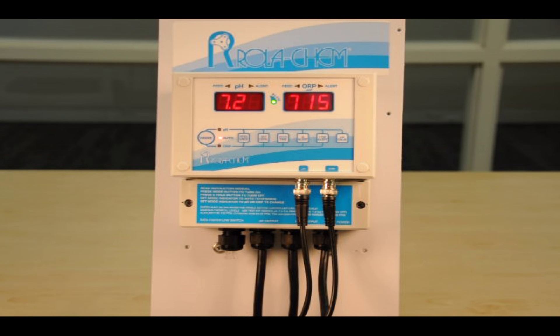In this segment I want to show you where the fuses are located for the 554 series Rola-Chem controller. The fuse may be burnt out if a feeder went bad and in doing so it sent amps back to the controller, thus burning out the fuse.